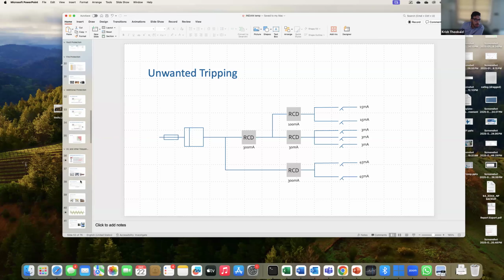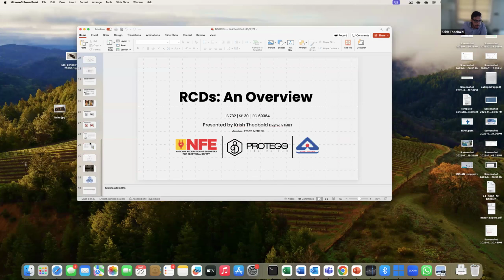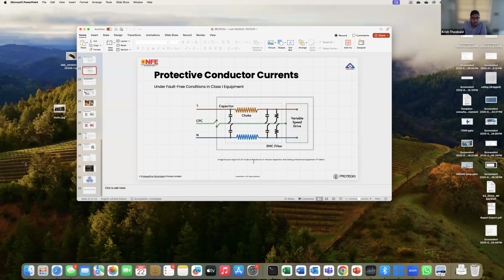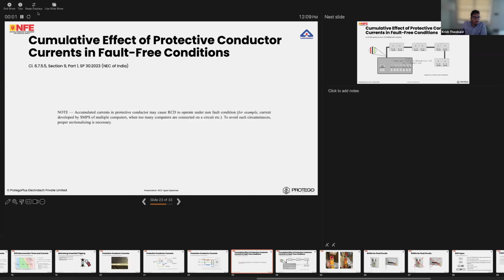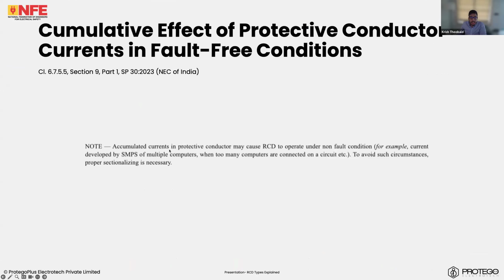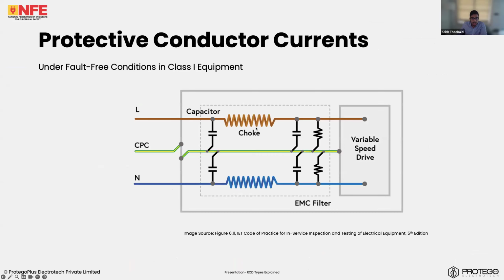I will show you. I have to get my own slides for this. I don't think this has been covered here. But basically, there is a nuisance tripping of RCDs that happens due to the currents in capacitors, like Gerard showed us. Now, I will just show you this where it shows this. Okay. See, the standard says that accumulated currents in protective conductors may cause an RCD to operate under non-fault conditions. For example, current developed by SMPSs of multiple computers, or too many computers connected to a circuit. To avoid such circumstances, proper sectionalizing is necessary.